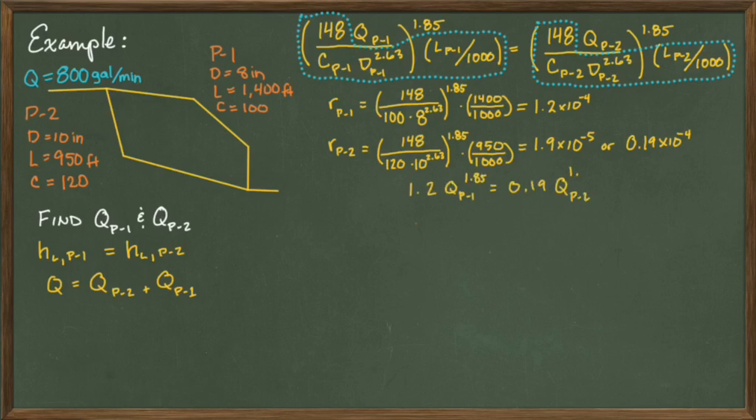We set the two pipes equal to each other to get 1.2 times q in pipe 1 to the 1.85 power, equal to 0.19 times q in pipe 2 to the 1.85 power. Solving for the flow rate in pipe 1, we get that equal to 1.85 root of 0.19 divided by 1.2 times the flow rate in pipe 2. And that gets us Qp1 equal to 0.37 times Qp2.